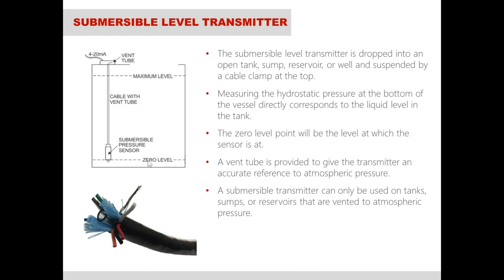For our 815LT, our submersible level transmitter, you have the same pressure sensor in there, except that it is measuring the hydrostatic pressure all around it. It's like when you go into a swimming pool and try to go down to the bottom: the deeper you go, the higher the pressure, and you can feel it in your ears. That's what we're doing here, measuring how much pressure is down in the depth of the tank or the vessel or the well or whatever you're trying to measure.